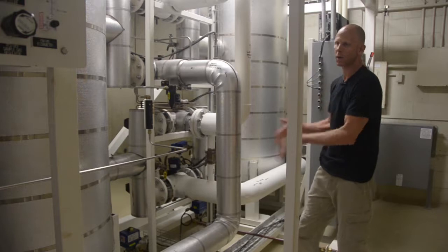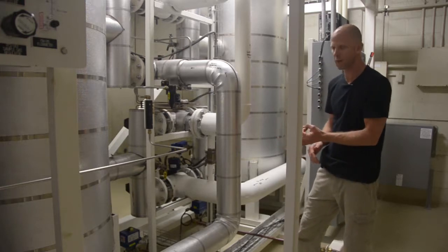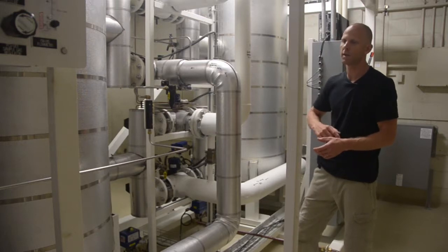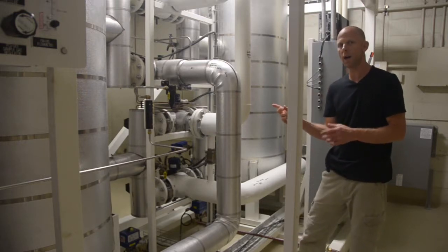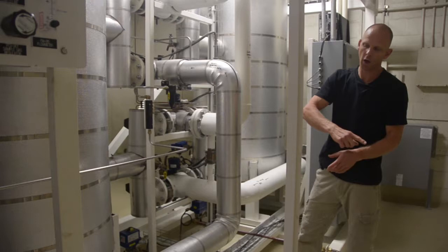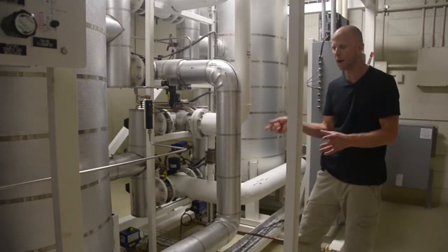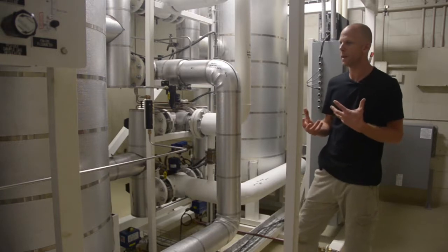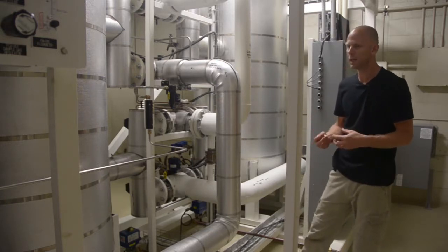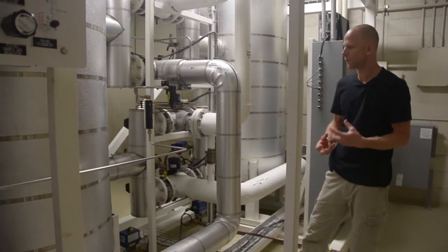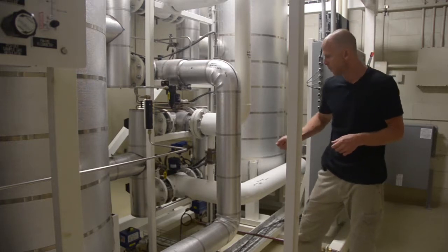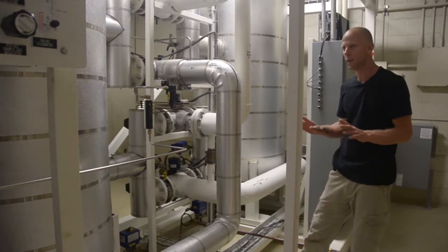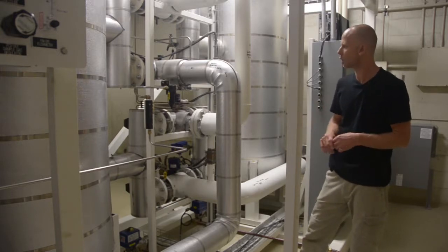If the plant is pretty much closed, apart from a small pressurization valve, the compressor is trying to push air through the plant. It reaches its maximum output pressure. It would then unload. So it would go through very rapid cycles or modulation cycles of loading and unloading. It's not necessarily bad for the compressor, but we would rather reduce the frequency of that modulation by opening the bypass valve to a degree and allowing the compressor to modulate in a more controlled way.